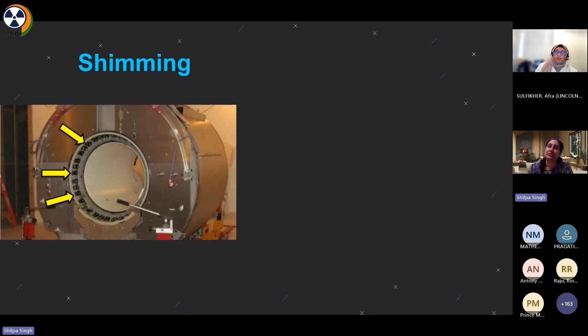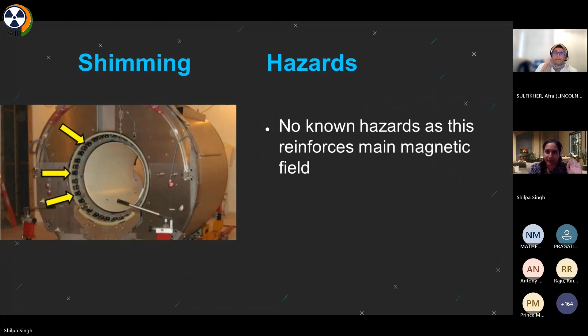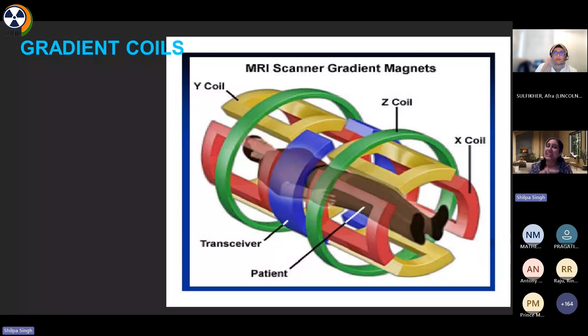Overall, I think you have understood that shimming is nothing but the same main magnetic field. So I can say it's a stable magnetic field, and there are no hazards associated with shimming. Gradient coils. We all know there are three sets of gradient coils, which have a magnetic field that varies from one direction to another. The z-axis coil, the slice selection axis, has two coils, one at each end of the bore, and they increase the magnetic field from one end of the bore to the other. Similarly, we have two sets of saddle-shaped coils, X and Y, placed in perpendicular directions, which are used for phase encoding and frequency encoding interchangeably.